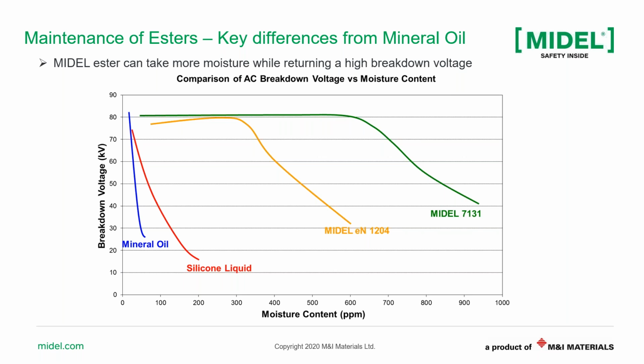Mineral oil is very sensitive to moisture, as we know, so any slight increase in moisture and the breakdown voltage will drop sharply. Silicone liquid is slightly better than mineral oil, but it is still sensitive to moisture. Now, because esters have these ester groups I mentioned, natural ester, which has three ester groups, can tolerate moisture without dropping the breakdown voltage up to 300 ppm, which is a hugely significant increase compared to mineral oil. But the best one there is the synthetic ester. You can reach up to 600 ppm moisture content before the breakdown voltage starts to drop.